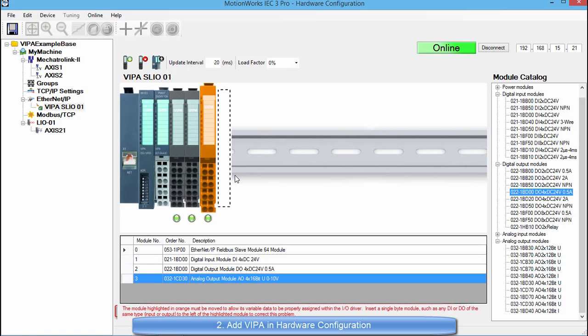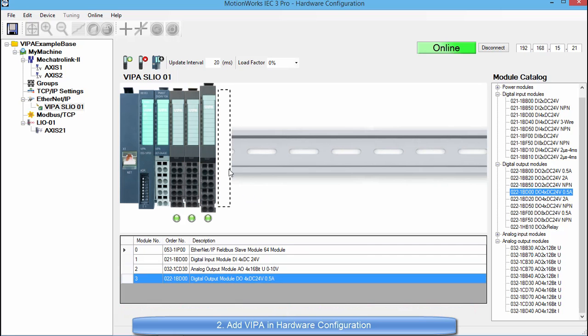Hardware configuration is saying that it cannot put that module there because it cannot set up the bus addressing correctly. One way to make the analog slice work in the system is to move the digital output card after the analog output card. This fixes the bus addressing issue. Since the analog output card is not needed let's remove it by clicking the delete slice button.